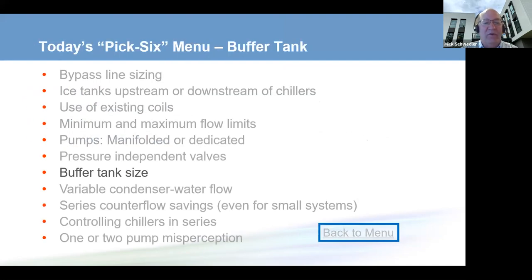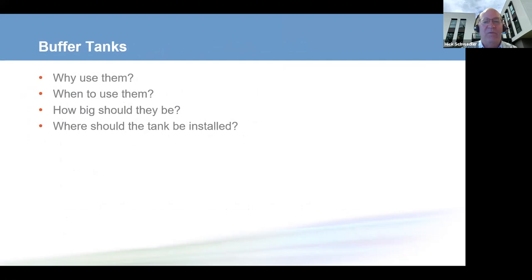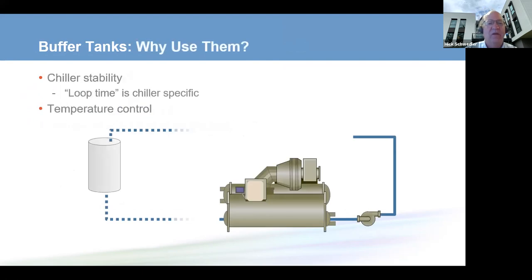Let's move on to the next one, buffer tank sizing. Why would we use buffer tanks? When, how, and where should they be installed? So the first is the why. In order to maintain a leaving chilled water set point, chillers will have a loop time dependent on their unit controllers, and the loop time for the smaller chillers with less sophisticated controllers is higher than the loop time for the larger chillers that have more sophisticated controls. And this is to keep the return water temperature from changing too fast and giving instability in our supply water temperature.